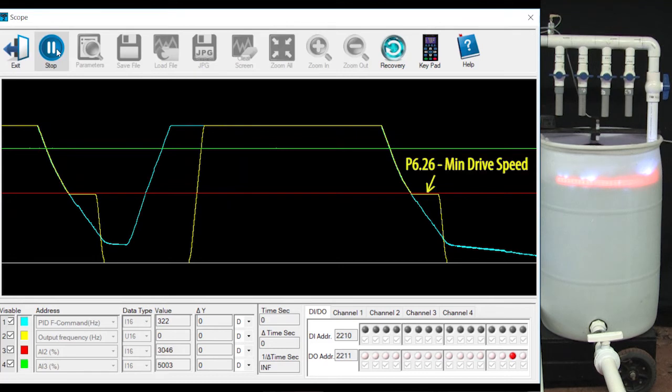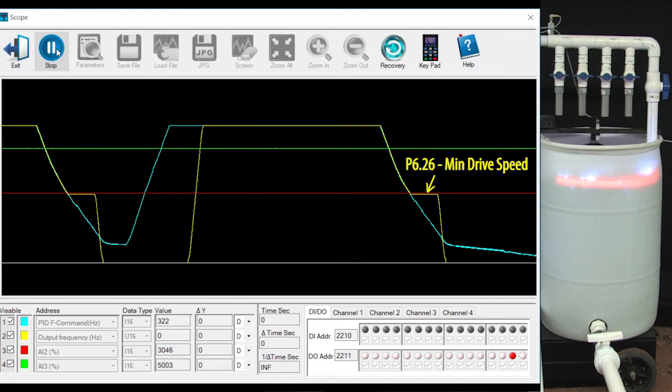This plateau is the output frequency you want the motor to run at during the delay. Maybe you don't want the motor to run at full speed during this time while you are topping off the tank. Or maybe you don't want it to run at all. You can set that speed using parameter 626, the min drive frequency. That will only be enabled during this sleep delay time.